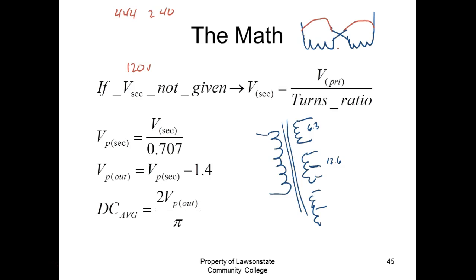And then we have multi-winding secondaries. This is where we can get multiple voltages off one primary, right? Transformers can get very expensive, but the problem is this guy right here might have 4 different voltages. This guy would be cheaper than having 4 transformers, and not only do I have to have 4 transformers, I got to have the space for 4 transformers. You'll see this done a lot, especially like on the trainer.